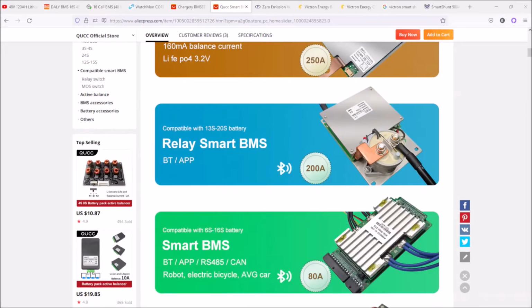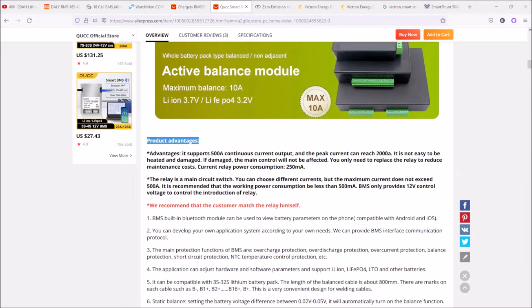I'd consider this hybrid, as it is an all-in-one type unit, although it keeps the power separated out off the board. They don't use FETs. It's a separate power contactor. The Off-Grid Garage did a really thorough review of this product, and it's one of my favorites. But look at the power consumption on the relay. It's 250 milliamps. If you do the math on that, you're talking about 12 kilowatt hours a month.